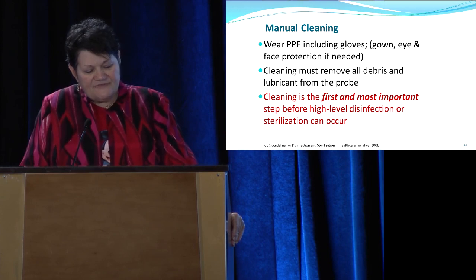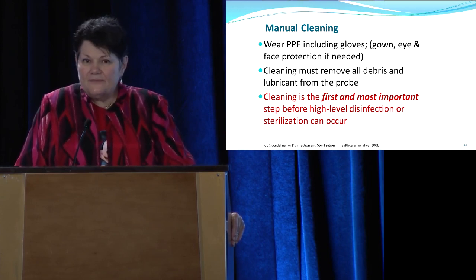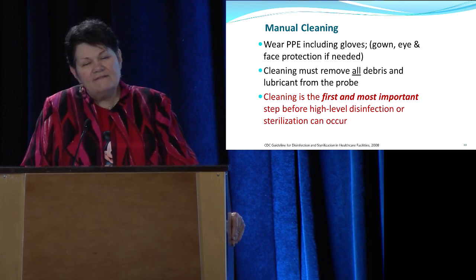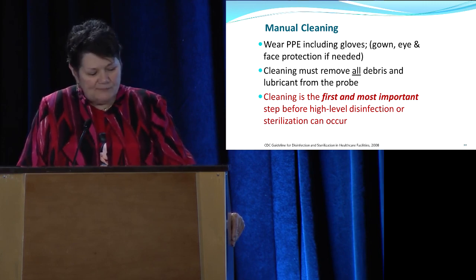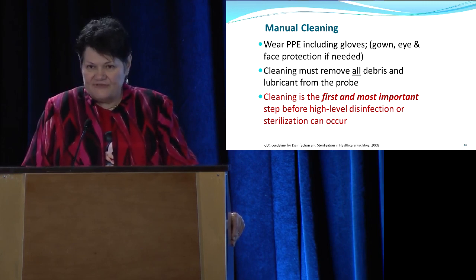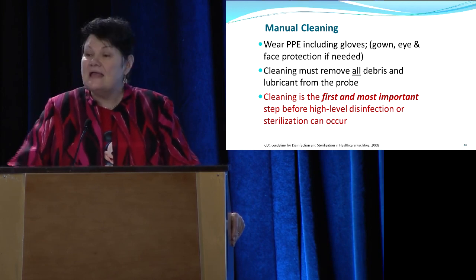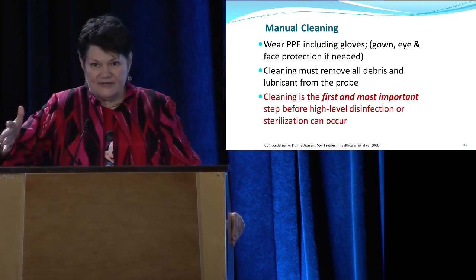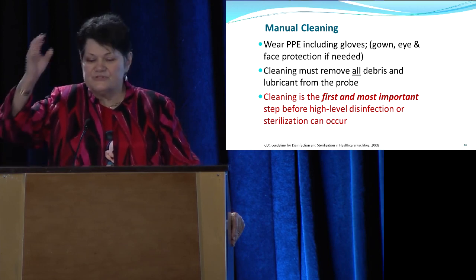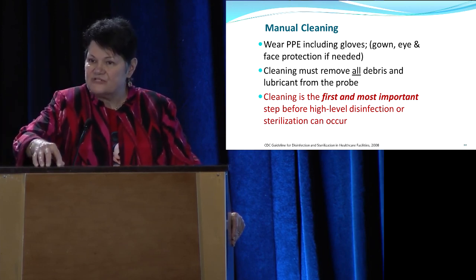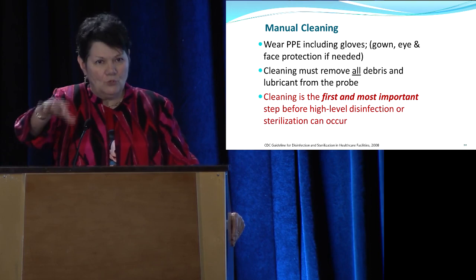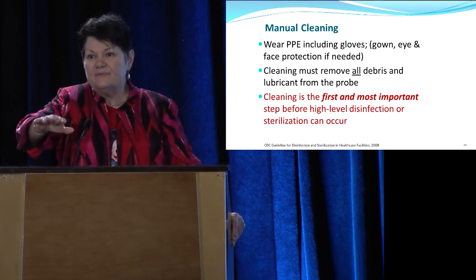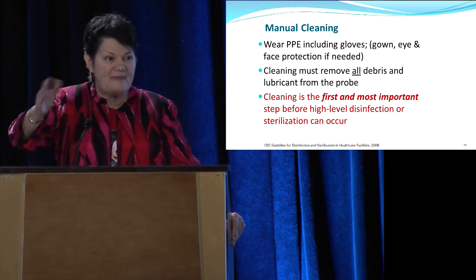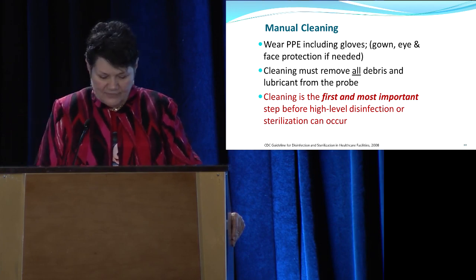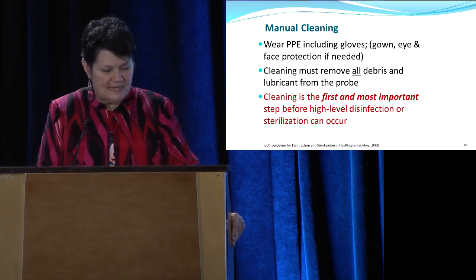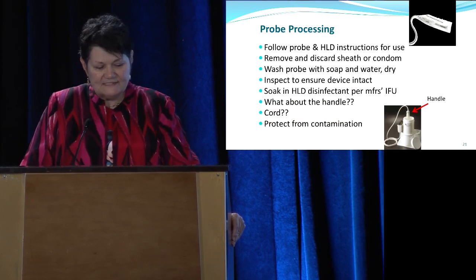The cleaning must physically remove all the debris and the lubricant from the probe, and cleaning is the first and most important step before high-level disinfection or sterilization can occur. If it isn't clean, you can't sterilize it or high-level disinfect it. There is no magic in the high-level disinfection solution or the autoclave that will clean it. It's got to be clean before it goes in, otherwise it just bakes on and organisms can remain in that crust that's on the device.